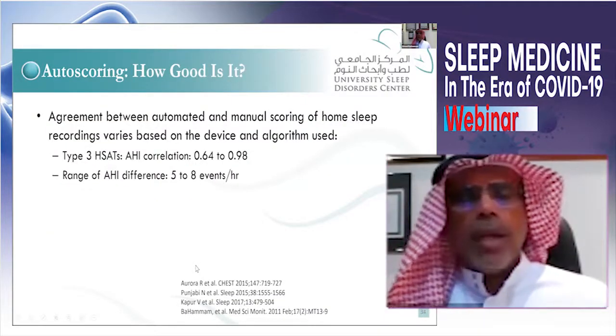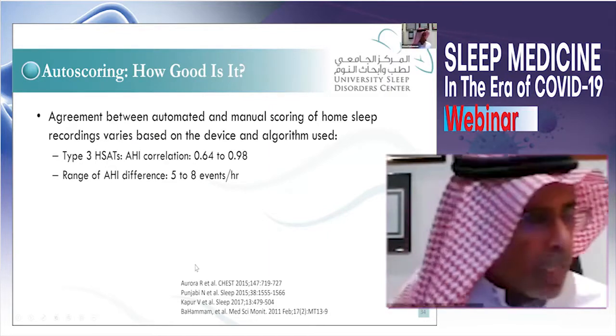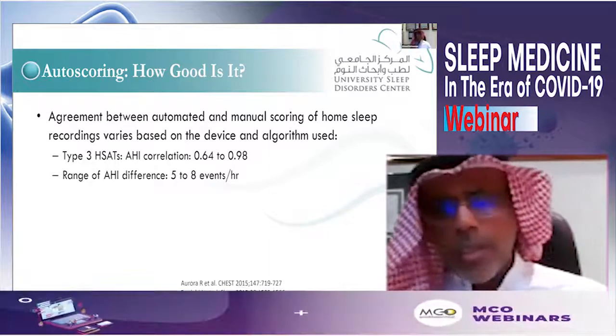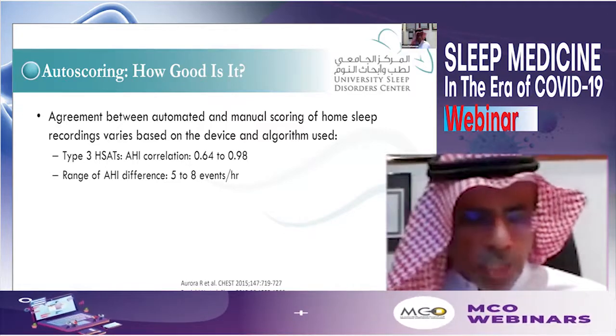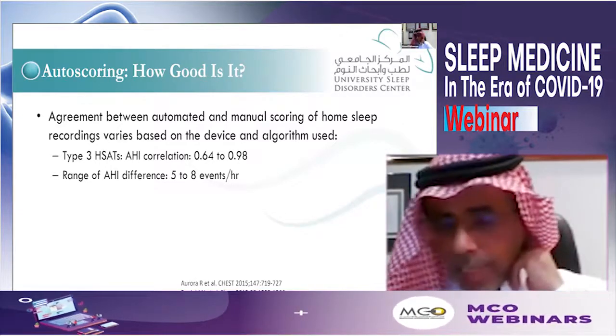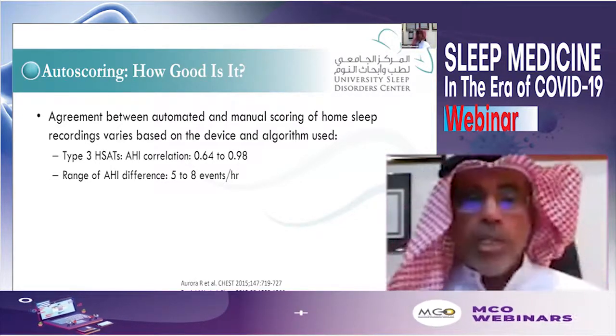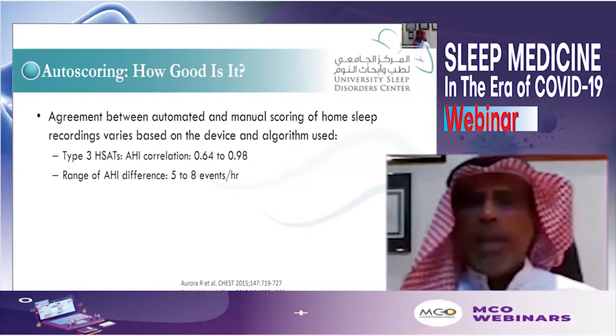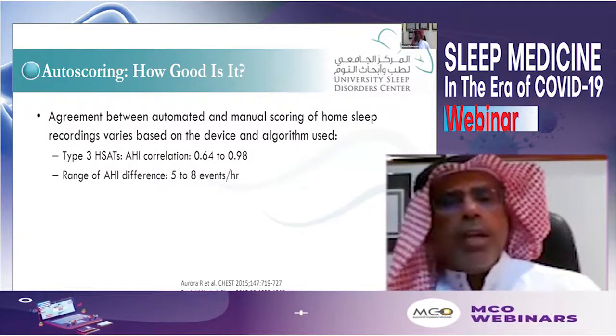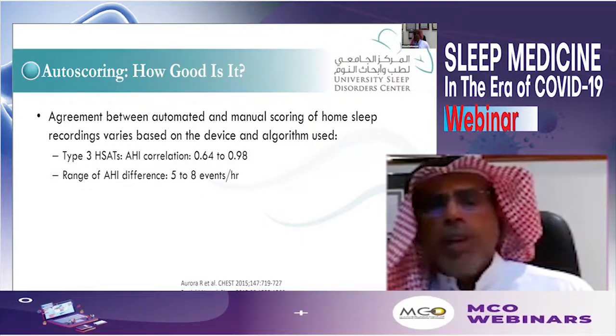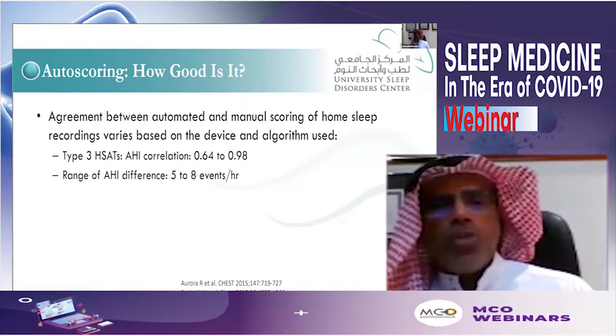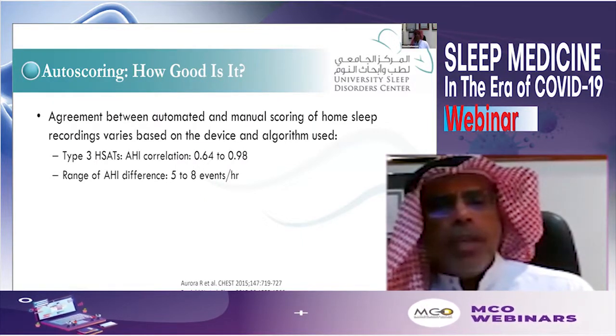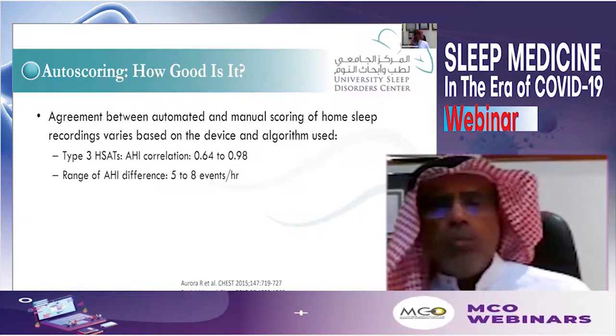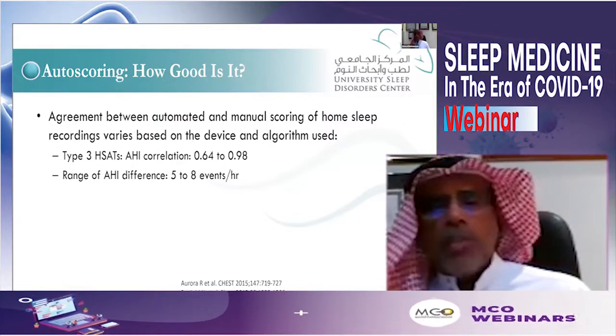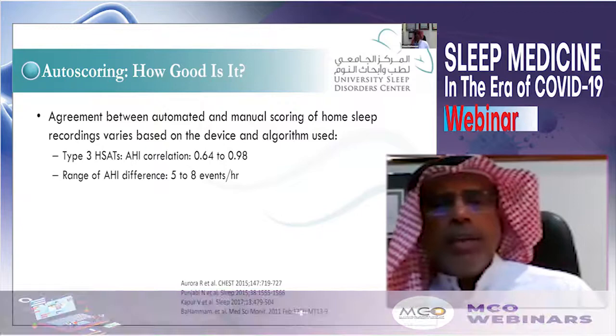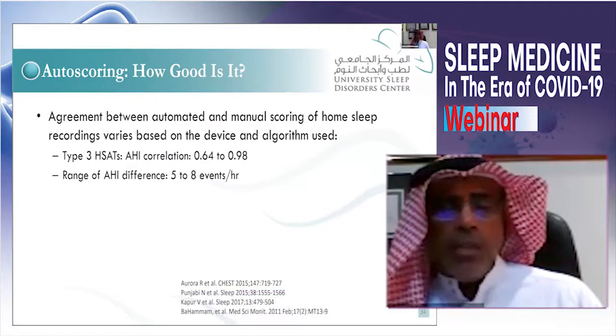Okay. And what about automated scoring? Many people do the home sleep testing, then click enter, and the machine will score it automatically. Still, the recommendation is to go for manual scoring, because the agreement between automated and manual scoring of home sleep recording varies based on the device and algorithm used. So for type 3, the AHI correlation varies between 0.6 to 0.98. 0.98 is good, but 0.6 may not be good. And the range of difference is 5 to 8 events per hour.